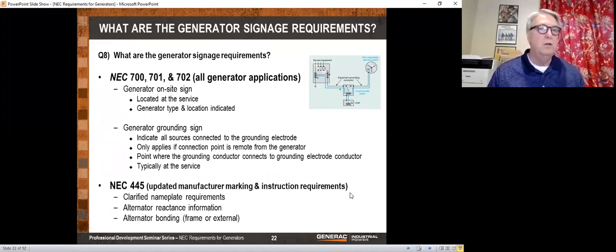What are the generator signage requirements? You need to have two signs on a generator. One is located at the service, and it tells you that you have a generator and where it is. It also should tell you the generator type, as in diesel or natural gas. And then you have to have a generator grounding sign, generally where you have your neutral to ground bond.